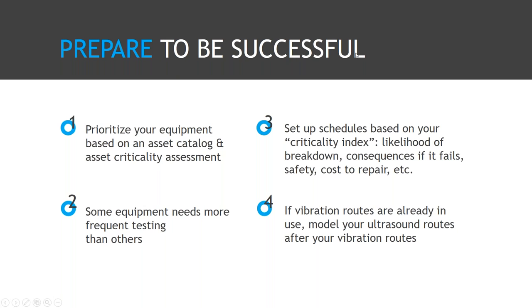Prepare to be successful: prioritize equipment based on an asset catalog and criticality assessment. Some equipment needs more frequent testing — some you can put on a monthly route, some quarterly, and some of your more critical assets are appropriate for continuous 24/7 monitoring. Set up schedules based on this criticality index, considering likelihood of breakdown, safety issues, and cost of repair. If you've already got vibration routes in place, you can model ultrasound routes right after those — you don't have to reinvent the wheel.